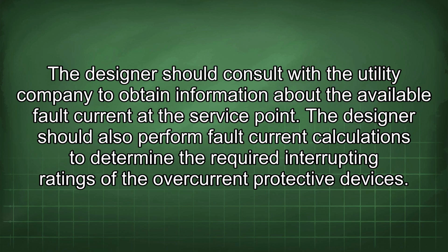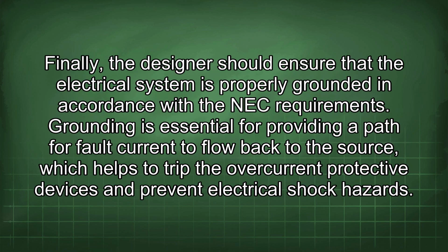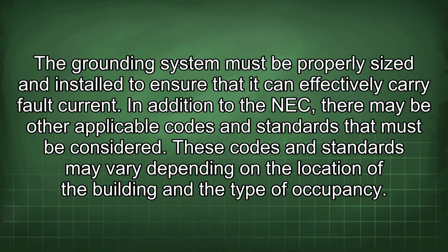The designer should also perform fault current calculations to determine the required interrupting ratings of the overcurrent protective devices. Finally, the designer should ensure that the electrical system is properly grounded in accordance with the NEC requirements. Grounding is essential for providing a path for fault current to flow back to the source, which helps to trip the overcurrent protective devices and prevent electrical shock hazards. The grounding system must be properly sized and installed to ensure that it can effectively carry fault current.